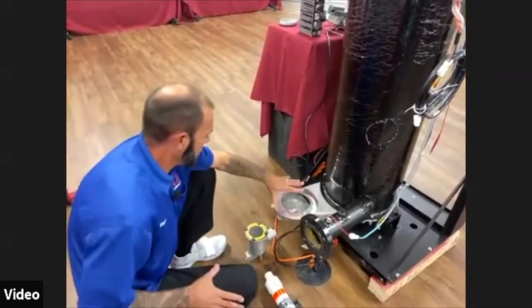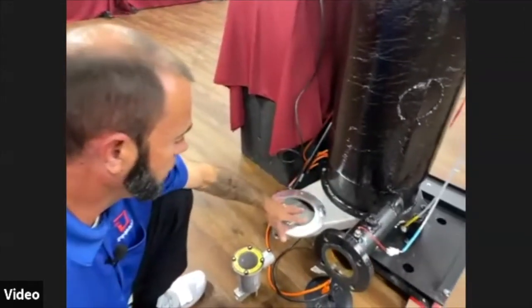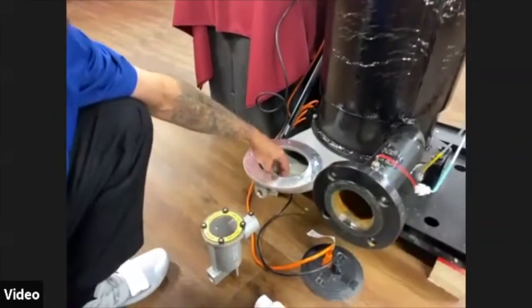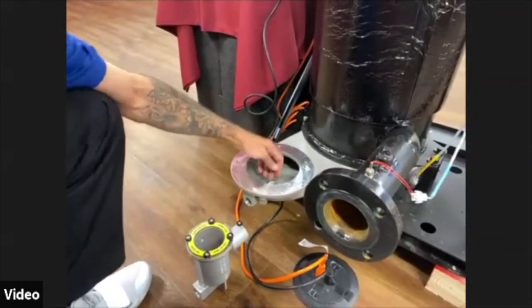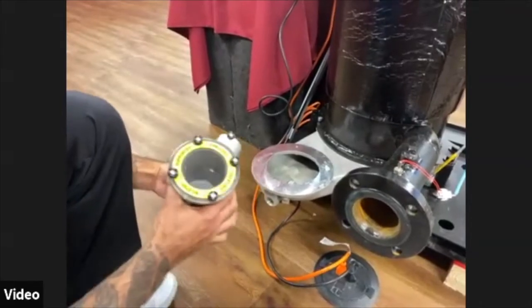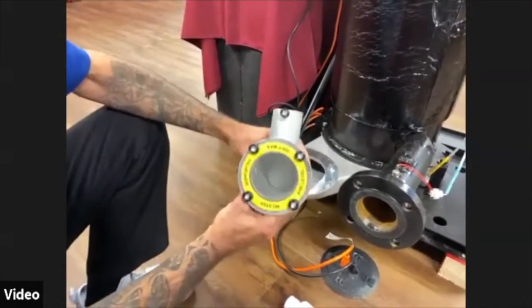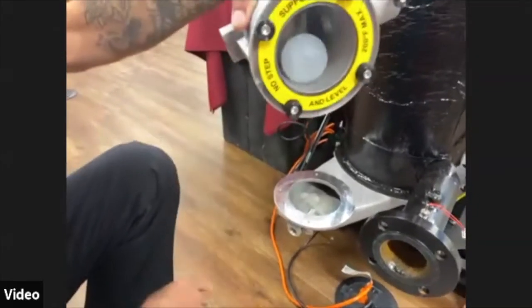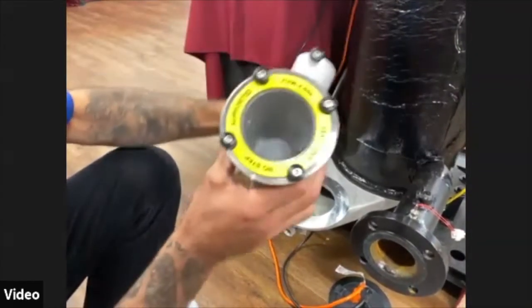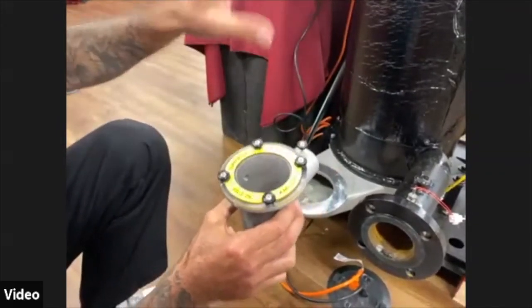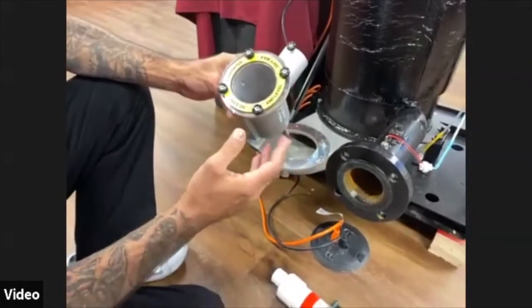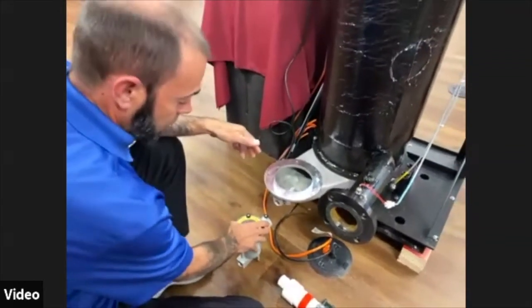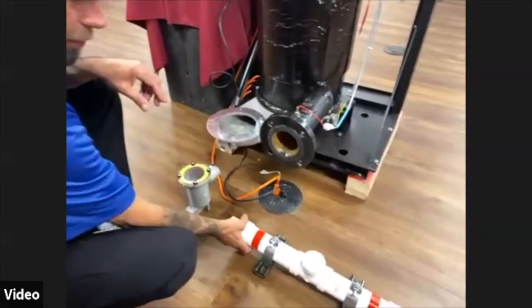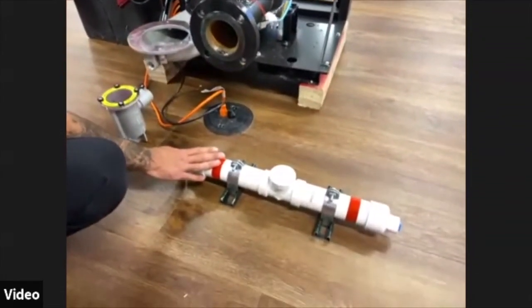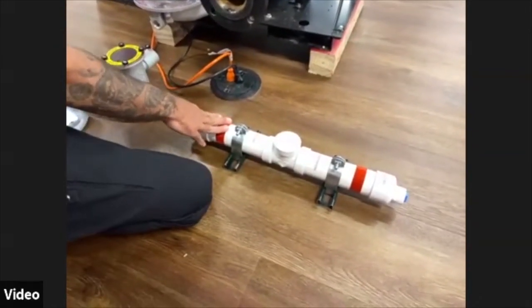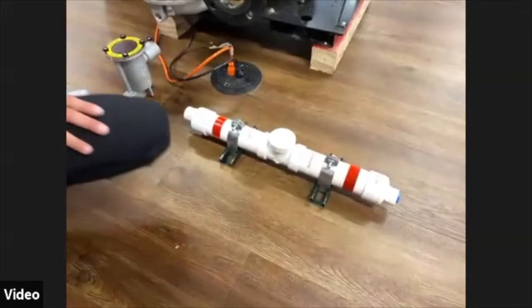Our exhaust manifold. So our exhaust manifold is bolted to the bottom of the heat exchanger. All our condensate and our flue gases travel through here, and they'll come out through here into our condensate trap. And our condensate trap has a poly ball in there. A poly ball seals the condensate, the flue gases from basically escaping into the atmosphere or into the mechanical room. Dylan will talk a little bit about maintenance on that. And out of there, we would generally go into our acid neutralizer to neutralize that condensate before it hits our floor drain. We come out and drop into our floor drain there.